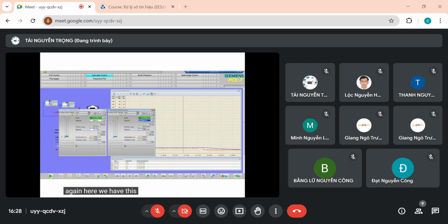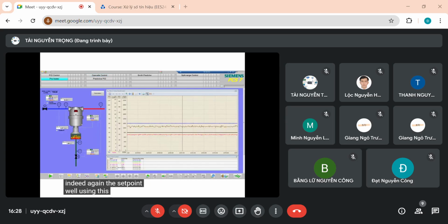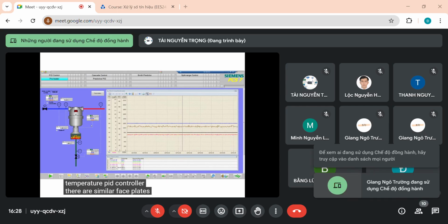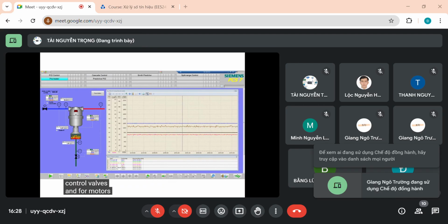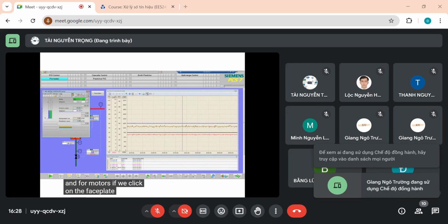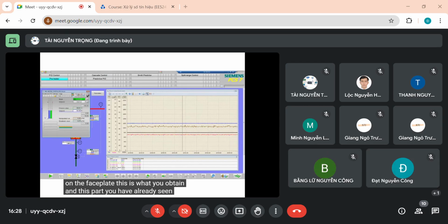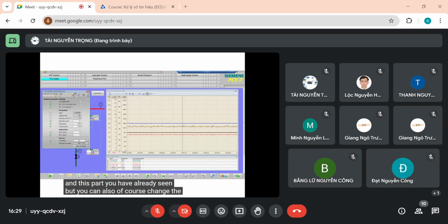Again, here we have this cascade control that is active, and what you see over here is indeed again the set point. Well, using this faceplate that you've seen before, it is possible to interact with the PID controller, here a temperature PID controller. There are similar faceplates for control valves and for actuators. If we click on the faceplate, this is what you obtain. In this part we have already seen, but you can also, of course, change the control parameters. Okay, so the parameters of the PID, so this is the PID control gain, the integral time constant, and the derivative time constant. We'll come back to that later.